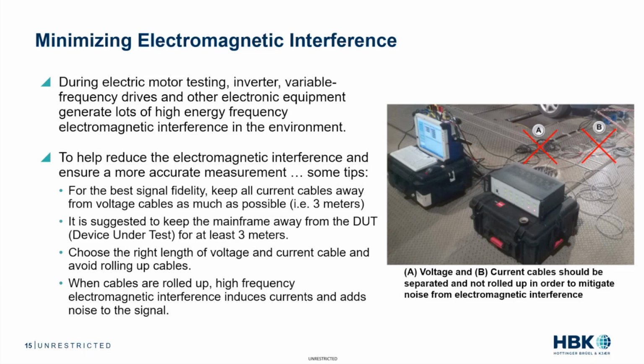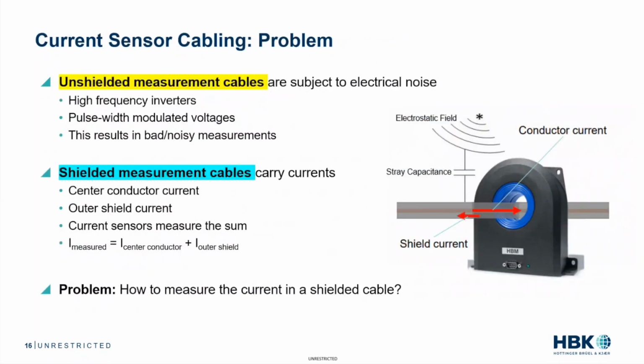Because when cables are rolled up, you're going to get high frequency electromagnetic interference, which is going to induce more currents and add noise to the signal. Well, let's talk about the sensor cabling. We'll start there. Some connections I've seen are unshielded measurement cables, and they're basically subject to electrical noise. You've got high frequency inverters, pulse width modulated voltages, and it's going to result in basically bad, noisy measurements. So you want to be sure and use shielded measurement cables.